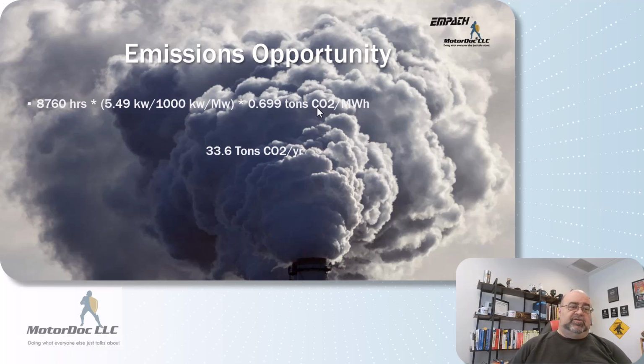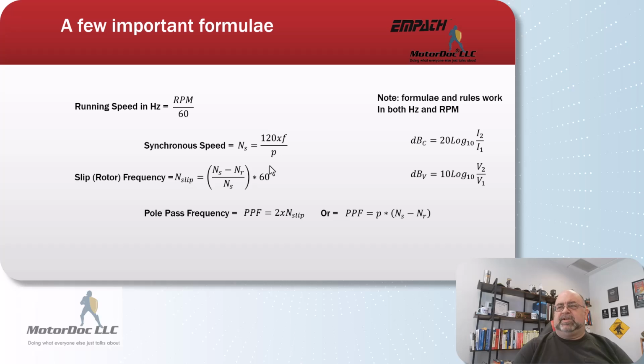CO2, because CO2 is heavier, per megawatt hour, and all the hype, but most companies have some type of carbon goal, and some actually have to deal with carbon credits. That is a reduction. Now, this is a different number than if I'm doing an inventory. You always use this value, because this is the avert value, to do it. So that is a potential reduction of almost 34 metric tons of CO2 by correcting the problems. It won't come out to that, probably closer to between 28 and 30 tons. There's always going to be some level of friction.